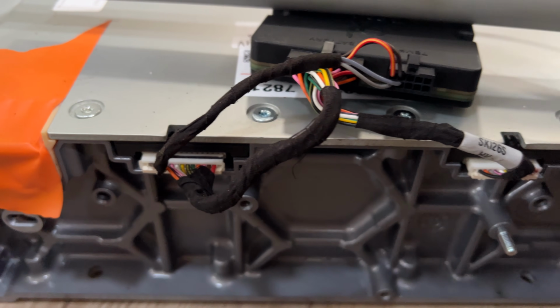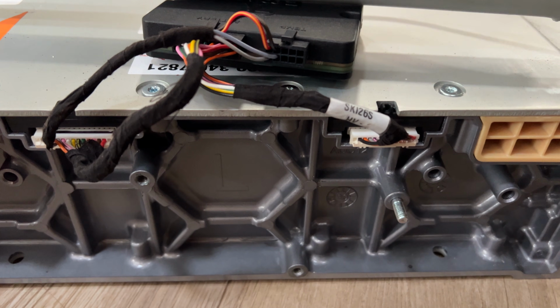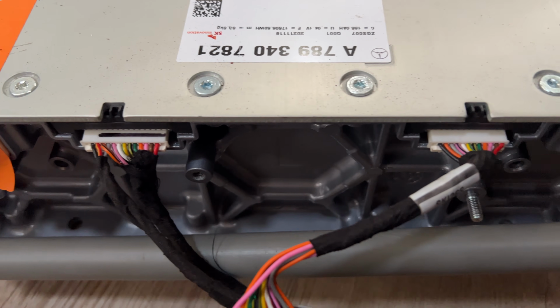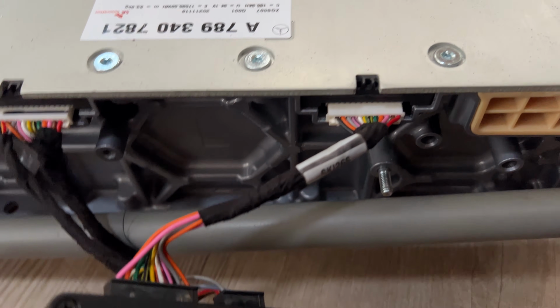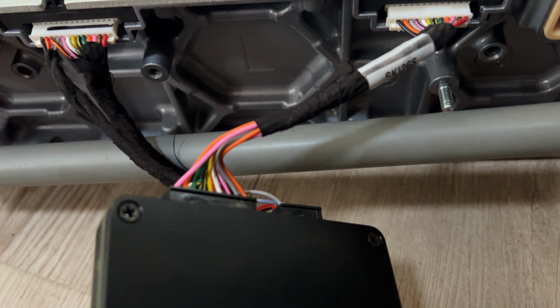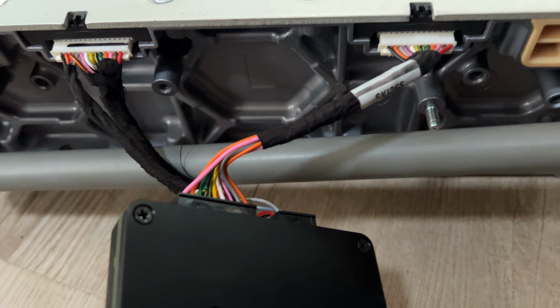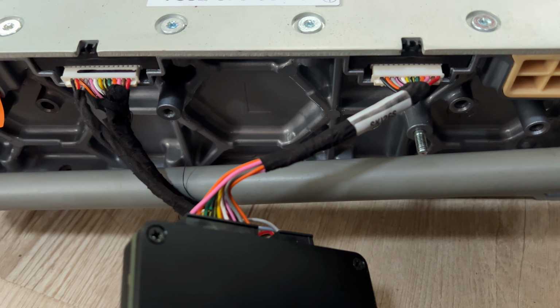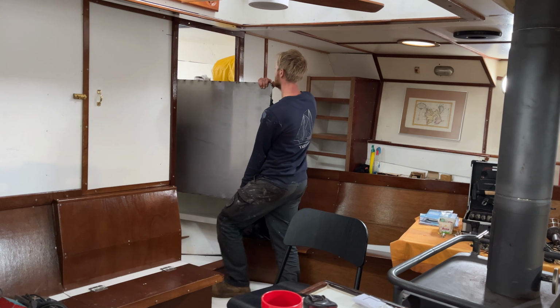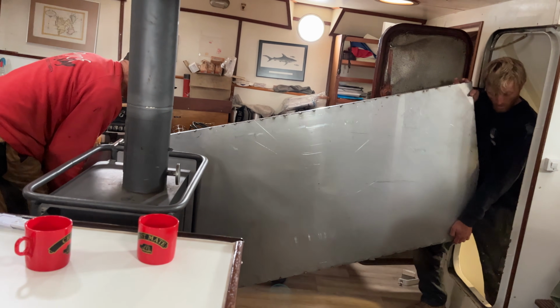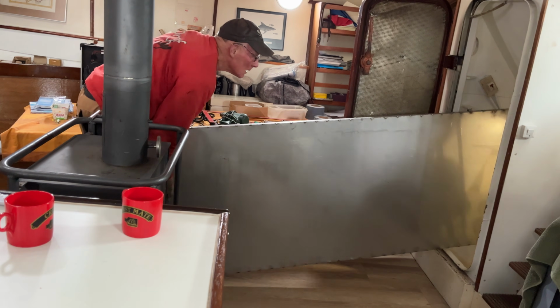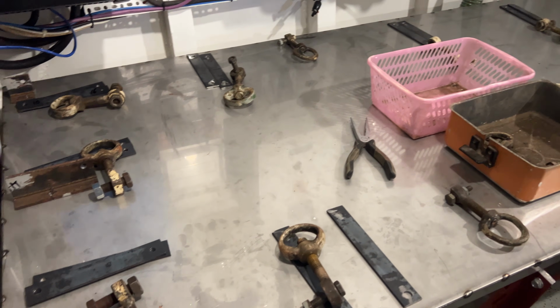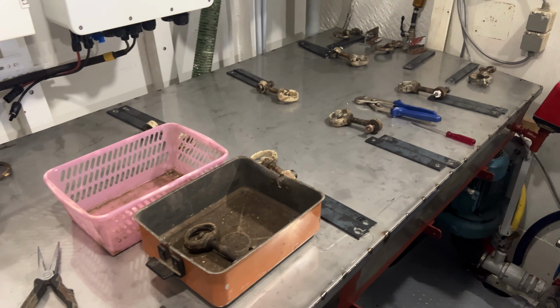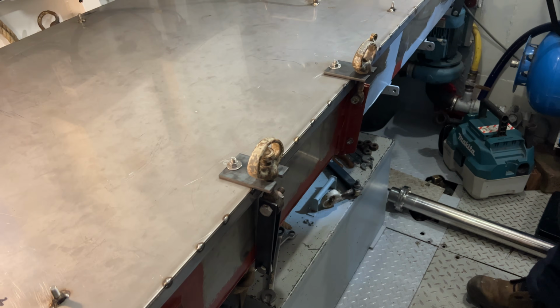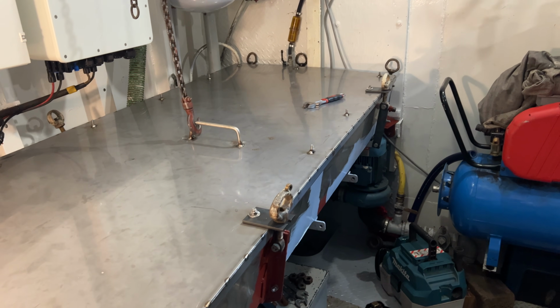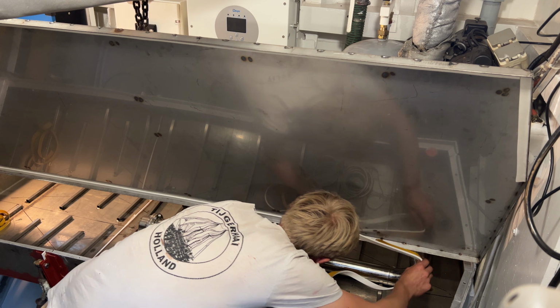They have extensive internal temperature monitoring, which you can see from the sheer number of small wires running from the modules to the battery group modules, sending all that data to the BMS. That level of monitoring is key for early fault detection inside the batteries. We didn't have enough material for the lid, so we had to order a new plate for that. To make sure it seals watertight, it gets screwed down with dogs that we still had laying around. And we're using high temperature silicone foam as a gasket.